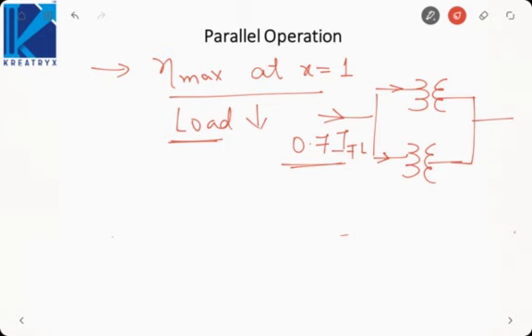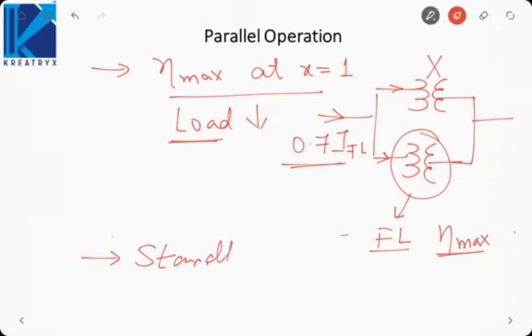So what to do is, we will switch off one transformer so that the other transformer can operate at full load. That is at maximum efficiency. To operate the other transformer at full load, we can switch off one of the transformers. Okay. Then the efficiency will be maximum or losses will be minimum. Okay. And the last thing is that a standby transformer is not needed. Okay, since we are operating two transformers in parallel, what is a standby transformer? A standby transformer is a backup transformer in case the main transformer fails. Okay, it is kept as a backup under the condition when the main transformer develops a fault and it has to be switched off.